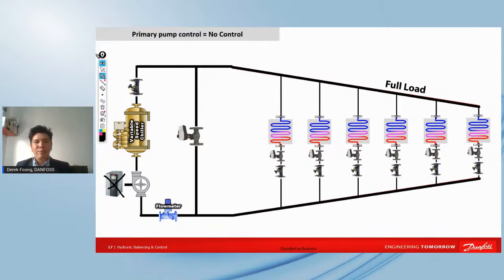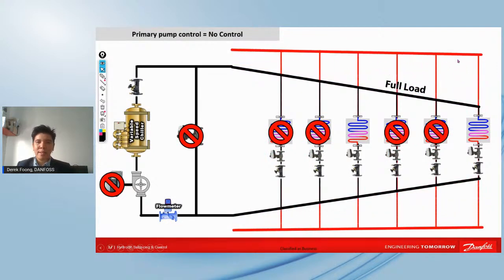So now, in full load, not much pressure is built up. So let's say all the control valves are open 100%. All right, and the bypass, let's say, is fully closed right now. Now, what happens during part load if there's no pump control? It's running on full speed, like what we saw just now. If it is running on full speed, the red color area is where the pressure builds up whenever the system runs on partial load. So that means some of the control valves are closed. The pressure will start to build up because of hydraulic interactivity. All right, so now you get the picture: no pump control, and all these red lines become wastage, more pressure than required. And you can see because of frictional losses, this ladder becomes a lot smaller, right? But when it closes, the pressure at the furthest point will also become as great as the pressure nearer to the pumping source in this case.